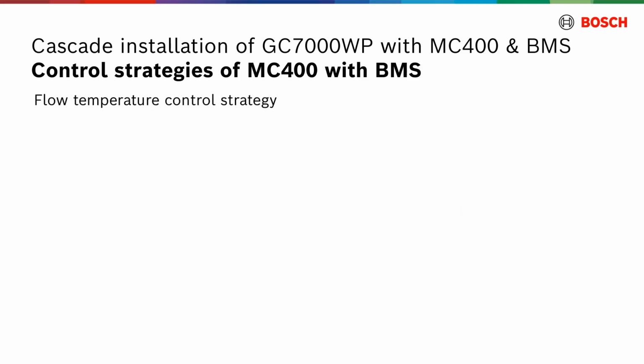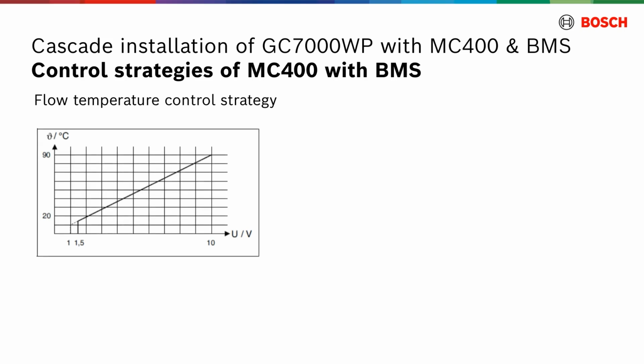Flow temperature control strategy. There is a direct correlation between the 0 to 10 volt signal and the desired flow temperature. The 0 to 10 volt temperature setting of the BMS is converted in the MC400 by an internal PI controller into a power setting for the individual heat generators. A minimum voltage of 1.5 volt is required to switch on the Cascade to prevent irregular starting of boilers from standby state. The Cascade is switched off if the voltage is lower than 1.0 volt. The voltage range between 0 and 1 volt cannot be used.